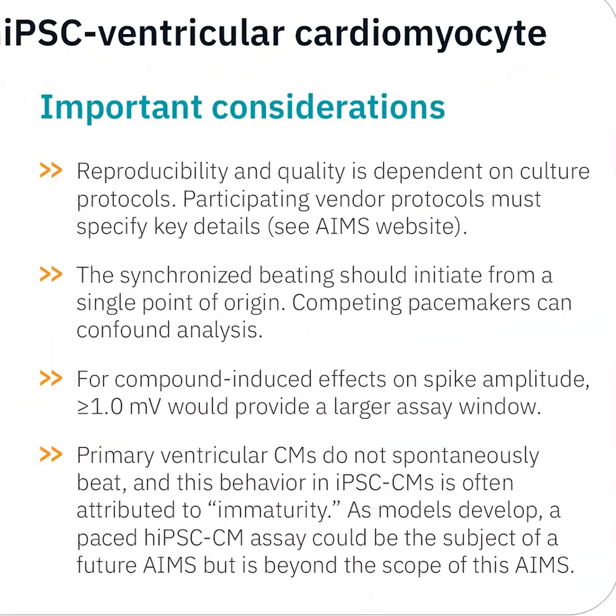Finally, it is important to consider the cell culture protocol. The reproducibility and quality of the iPSC cardiomyocyte model's functional activity is dependent on the cell culture conditions. Consequently, participating cell vendors must specify key details in their recommended protocol.